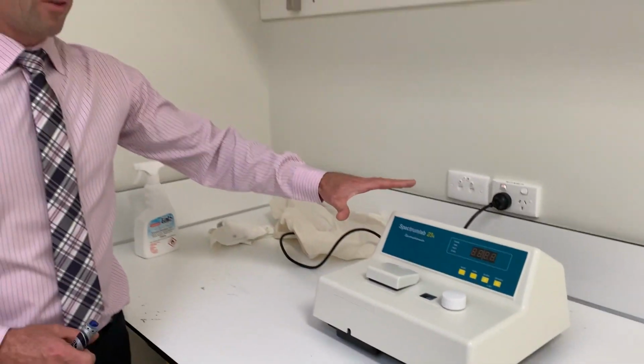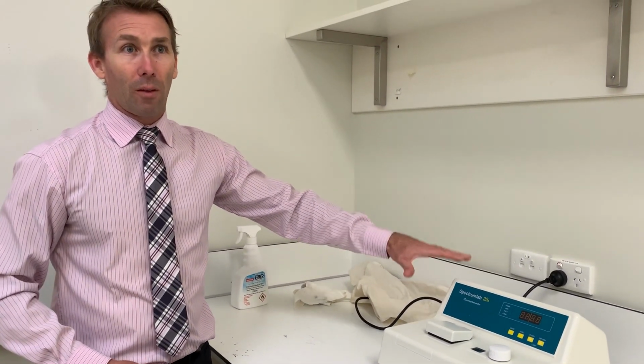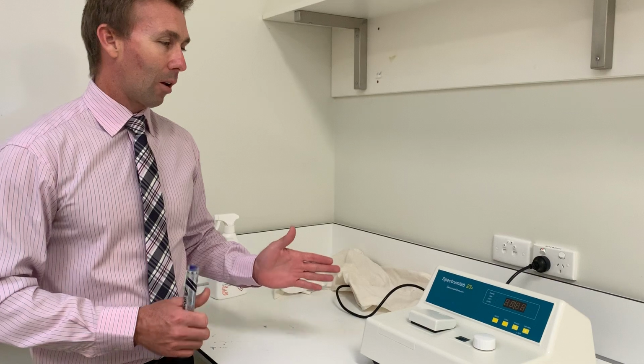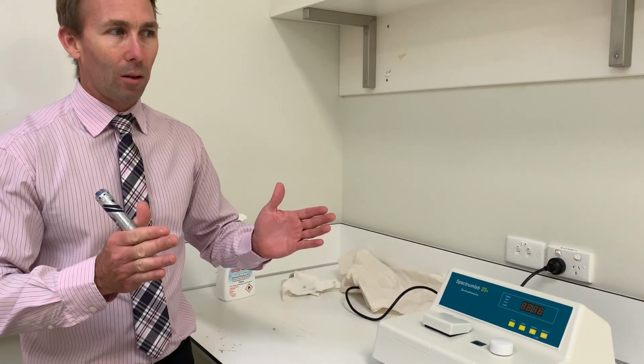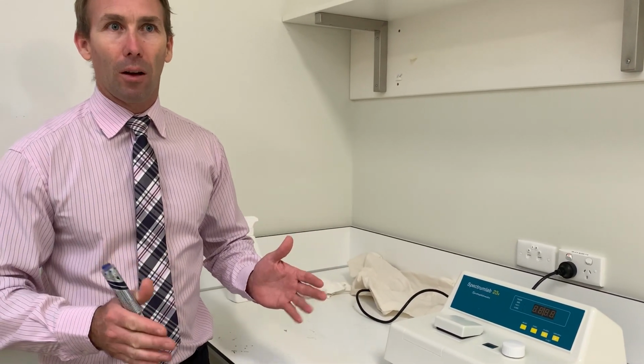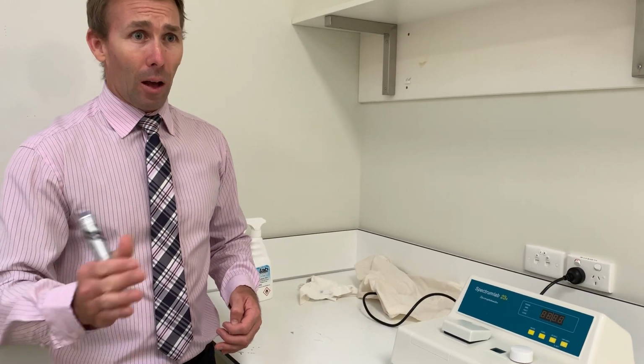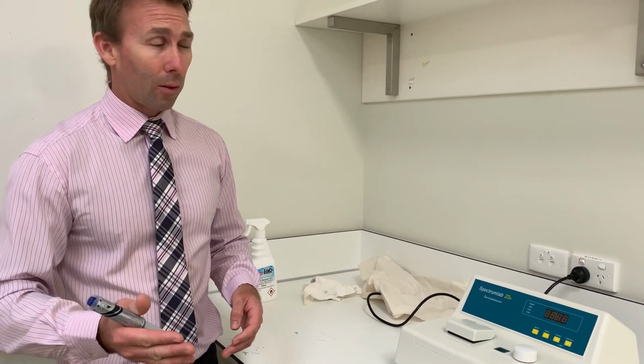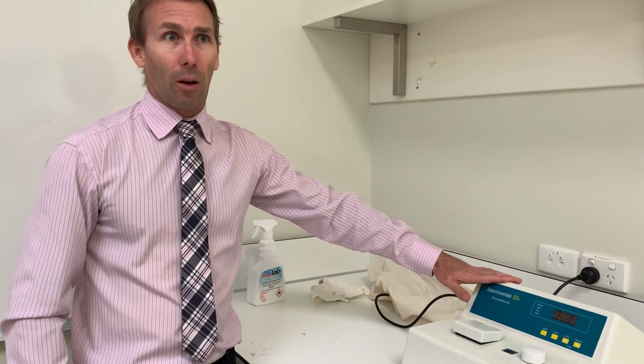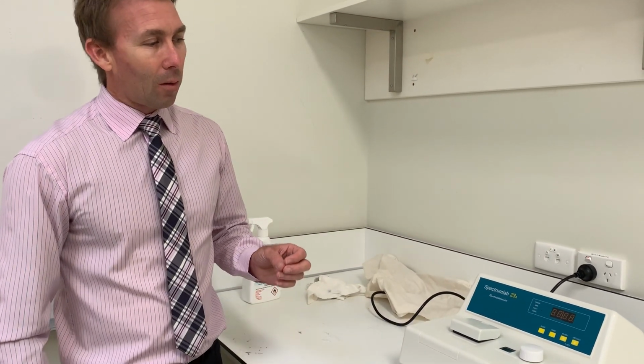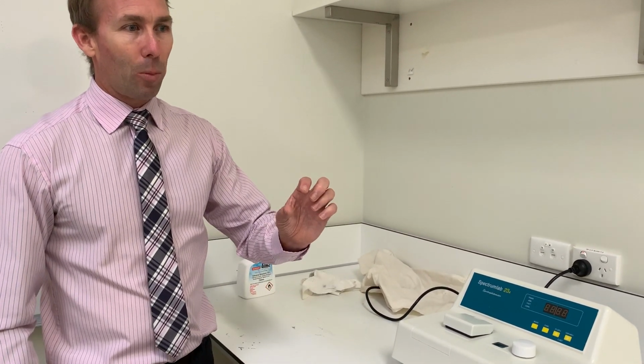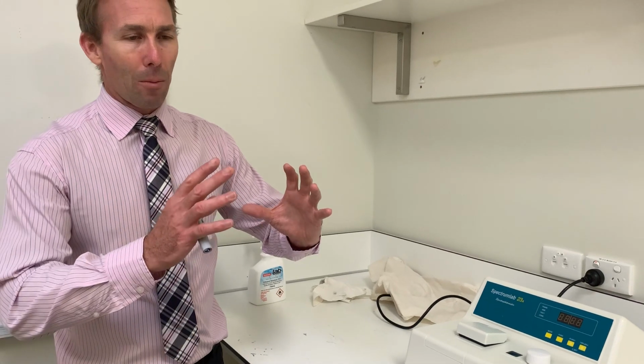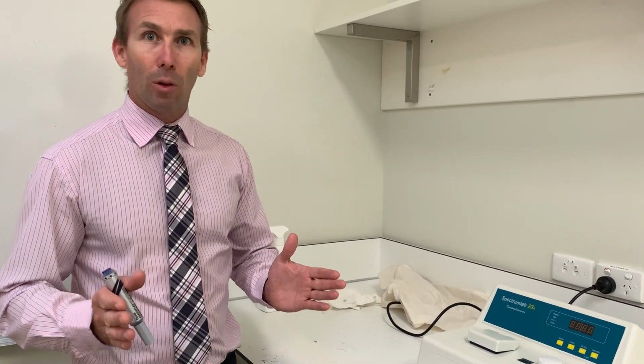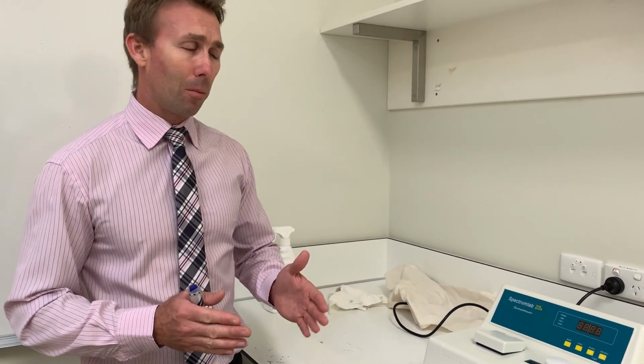So that wavelength range that we just talked about, that's all in the visible range, and in the visible range, rule of thumb is if it's coloured, and you can see that it's coloured, and the colour change is going to change with concentration, then this one here will get your results. Some samples that have double bonds in them, organic aromatic compounds, will actually detect below that 350 nanometers and maybe around 200, 250.